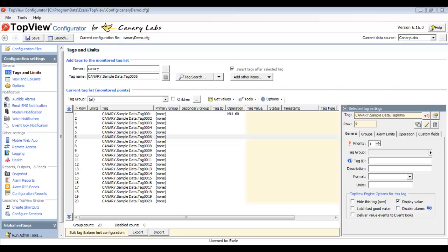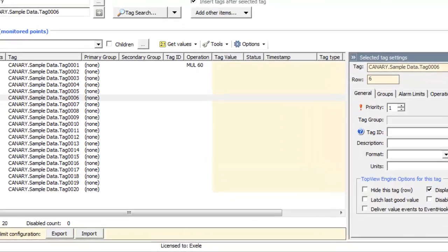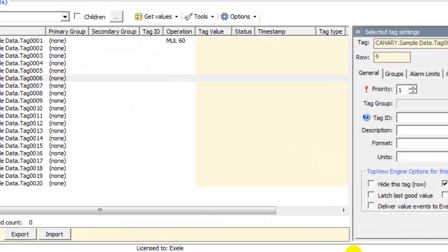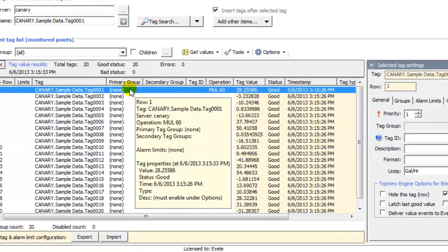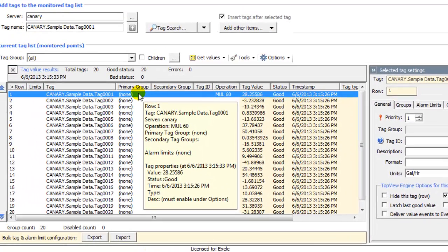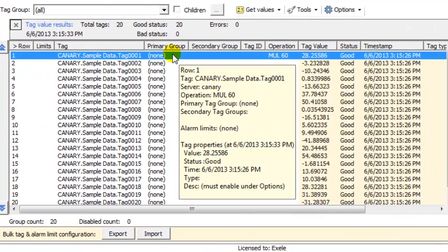The next step is to configure alarm limits for a few of the monitored tags, so I've returned to the Configurator. Before I start, I'd like to retrieve the current values of the tags into the Configurator, and to do this, I click Get Values above the Tag List. I will configure alarm conditions for two of the monitored tags. The first tag is the flow in gallons per minute, but we've converted this to gallons per hour in the Top View Engine. If an operation exists, the alarm limits are compared to the result of the operation, not the original tag value.